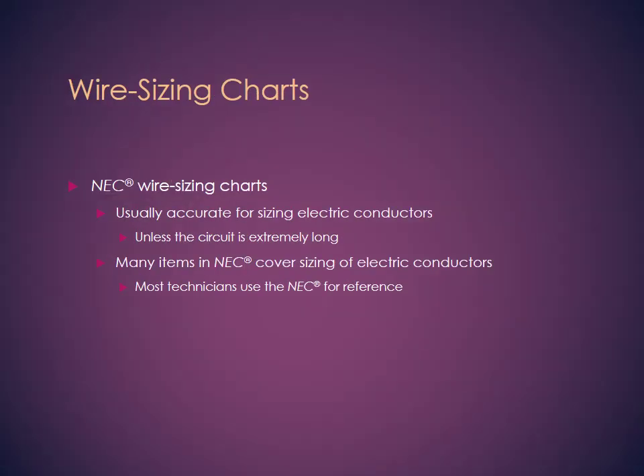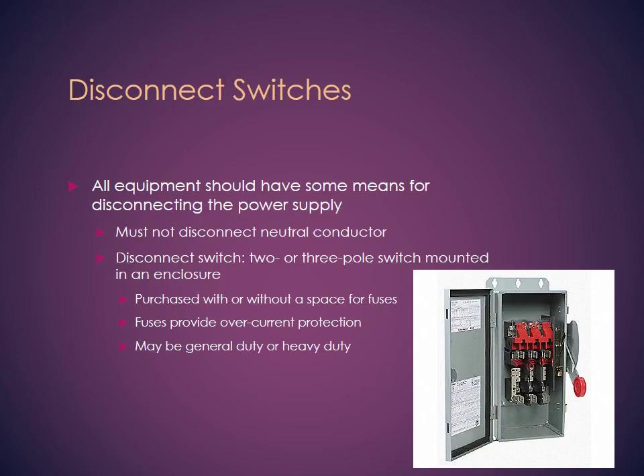We need to know about disconnect switches. Every piece of equipment needs to have a disconnect switch, especially for heavy loads like an air conditioner or a boiler. And usually we connect through the hotline. So if we have three disconnects here, that means we have three hotlines. The disconnect switches should be on the hotline, not on the neutral. Some of them have fuses, some of them don't, depending on the load and the code.